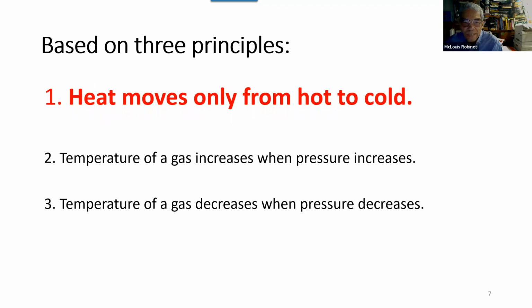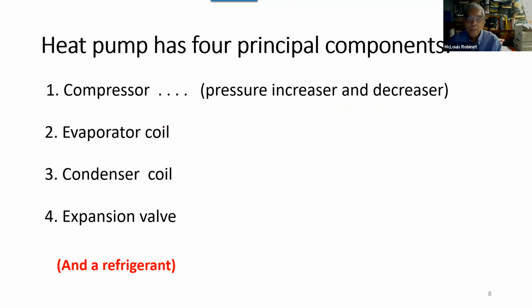This cycle is based on three physical principles. The first and most important one is that heat travels only from hot to cold. Thermal energy moves only from hot to cold, regardless of how small the difference. The second is that the temperature of a gas increases when the pressure increases, and decreases when the pressure decreases. A heat pump has four major components: a compressor, which increases and decreases the pressure, an evaporator coil, a condensing coil, and an expansion valve. And we can't forget the refrigerant, also a major thing.